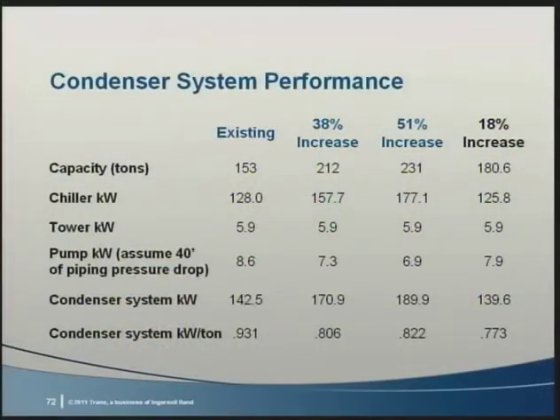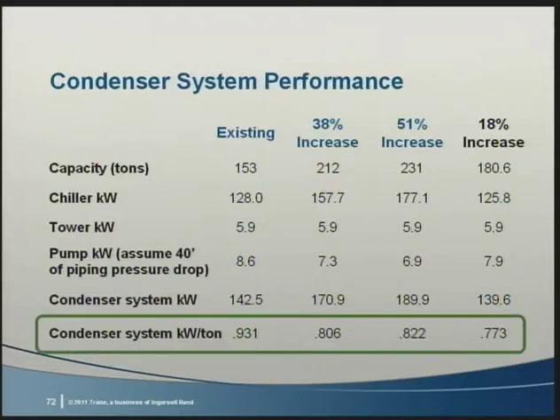But the owner pays for the entire system to operate, so let's look at how this affects system power. The existing cooling tower fan used 5.9 kW, and the condenser water pump used 8.6, with the chiller using 128 kW. When a larger chiller is installed, there are more tubes in the chiller's condenser, and the condenser water pressure drop goes down. This means that the pump kW can be reduced, most likely by throttling its flow using a variable speed drive. We'll talk about that more in a few minutes.